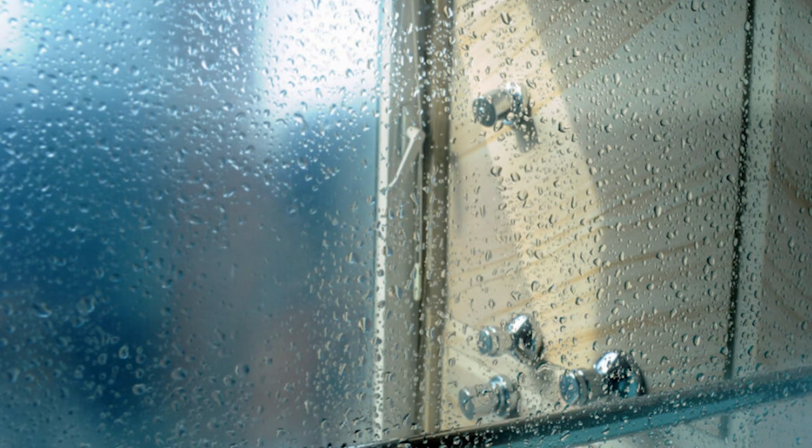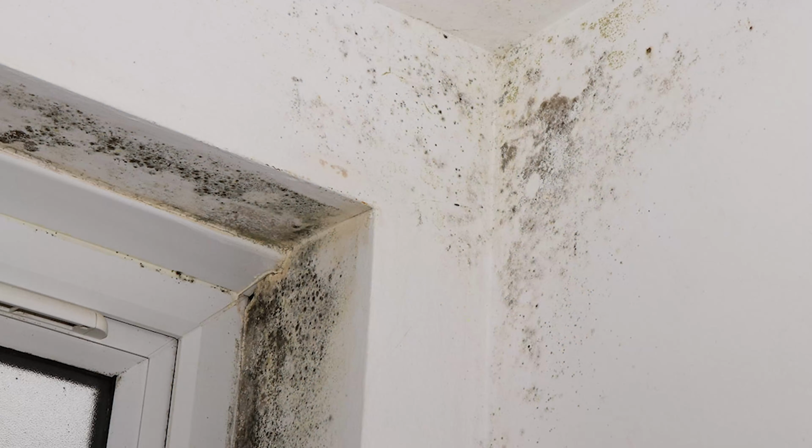So every time we turn the shower on, all the surfaces in here are below the dew point. We get condensation all over the place, all over the walls and ceiling, and mildew starts showing up in some of the corners here. So I'm going to try to reduce air leakage as much as possible to raise the temperature here and do something about the condensation and the mildew. One thing I haven't yet touched is the skylight here.